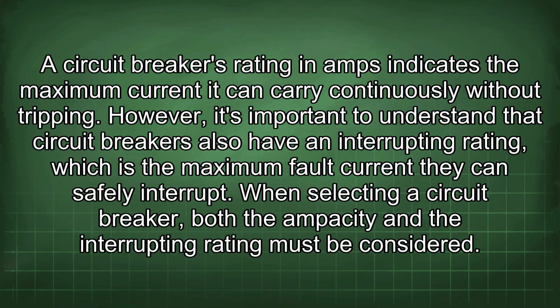The circuit breaker's rating in amps indicates the maximum current it can carry continuously without tripping. However, it's important to understand that circuit breakers also have an interrupting rating, which is the maximum fault current they can safely interrupt. When selecting a circuit breaker, both the ampacity and the interrupting rating must be considered.